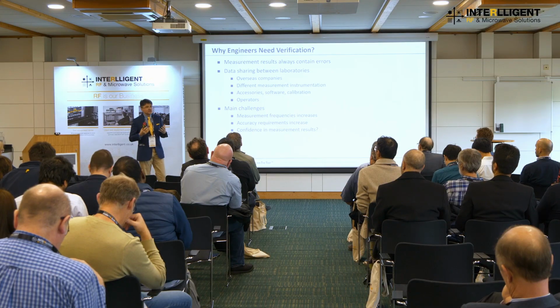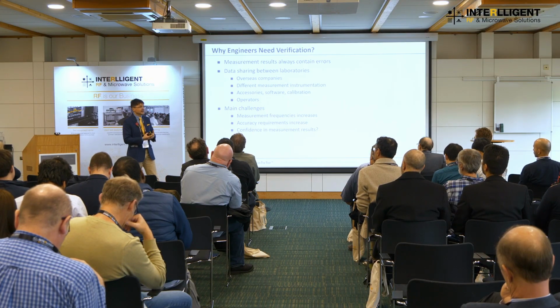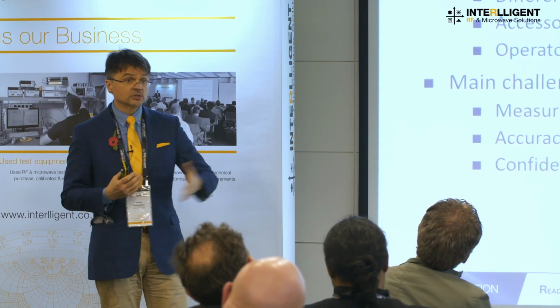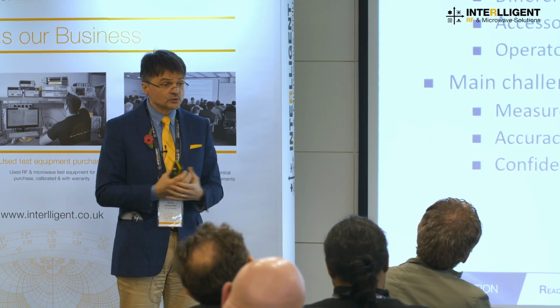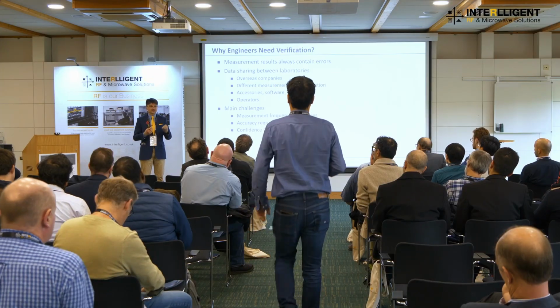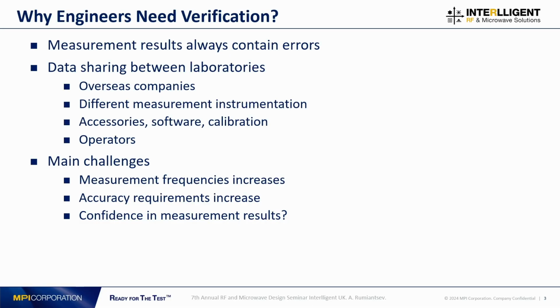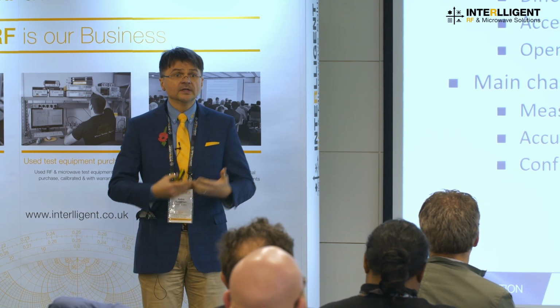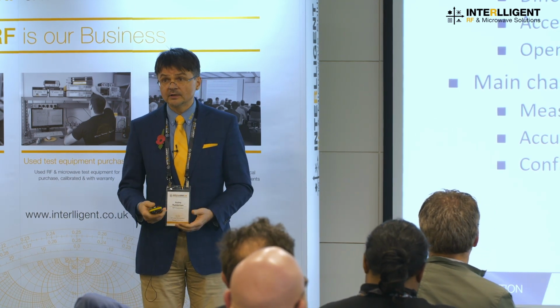And the main challenge today is that the frequency of the measurements that we need to characterize our device under test increases. At the same time, the requirements for the accuracy of the measurements increase as well. And usually when we talk about the confidence in the measurement results, it's inversely proportional. So the higher the frequency is, the less we're confident in the data we measure, because it's really complicated to understand what exactly is going on specifically in the wafer level environment.